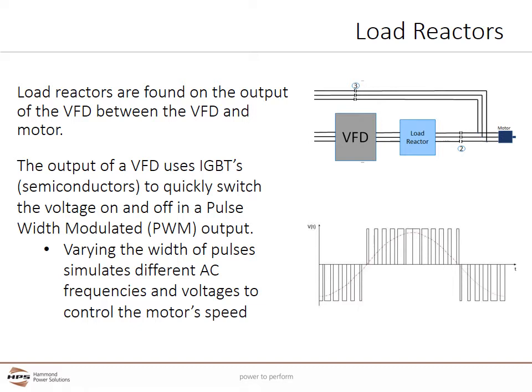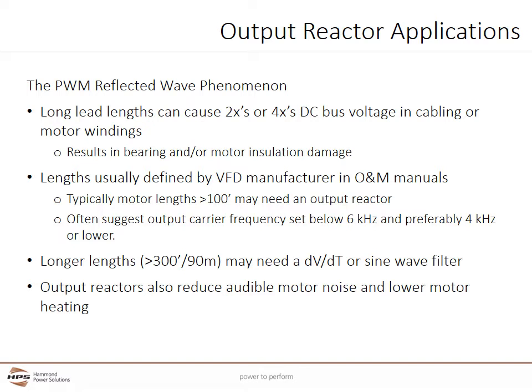Load Reactors are found on the output of the VFD between the VFD and the motor. The HPS Centurion CRX line reactors can be used interchangeably on the line and load side of the VFD. The output of a VFD uses IGBTs, a type of semiconductor, to quickly switch the voltage on and off in a pulse width modulated (PWM) output. Varying the width of the pulses simulates different AC frequencies and voltages to control the motor speed. The output of a VFD can cause the PWM reflective wave phenomenon. Long lead lengths can cause voltage spikes of 2 or 4 times the DC bus voltage to appear in the cabling or motor windings.